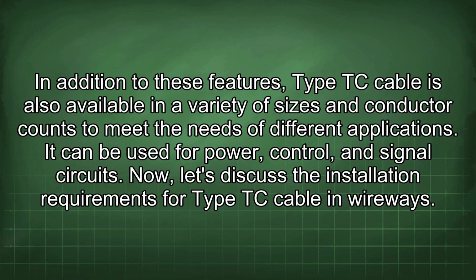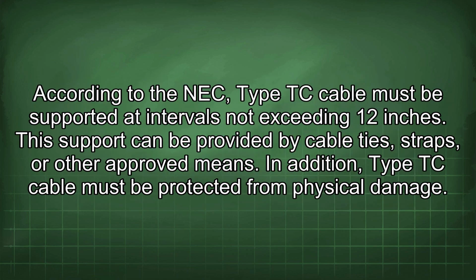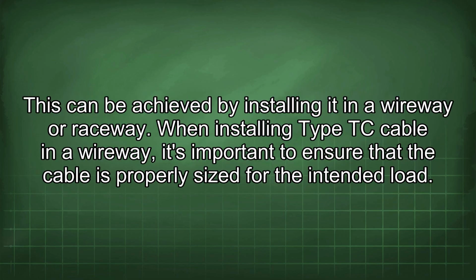Now let's discuss the installation requirements for Type TC cable in wireways. According to the NEC, Type TC cable must be supported at intervals not exceeding 12 inches. This support can be provided by cable ties, straps, or other approved means. In addition, Type TC cable must be protected from physical damage. This can be achieved by installing it in a wireway or raceway.